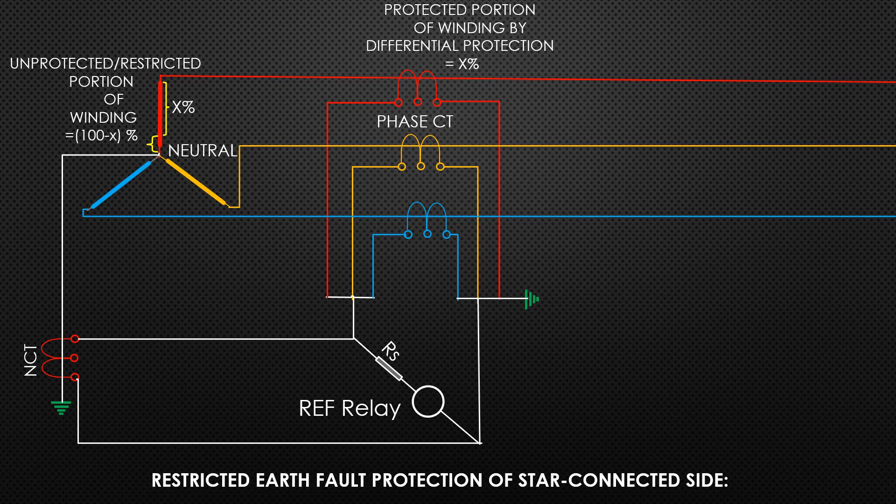Hence fault current would be low. If the relay is kept at a setting to sense such faults, it has to be too sensitive and would therefore operate for spurious signals, external faults, and switching surges. Therefore, a separate earth fault relay is incorporated in the protection circuit, operating for earth fault current of the order of 5 to 10 percent of rated winding current. Such settings protect a restricted portion of the winding, hence the name Restricted Earth Fault protection.